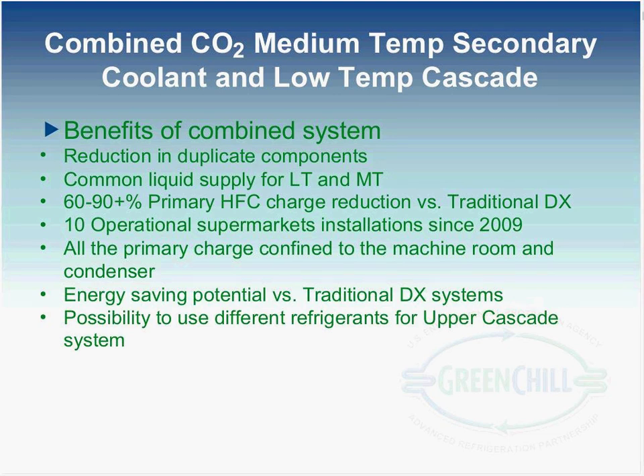Ten of this type of system have been operational since 2009, so it is a relatively new technology, but with good experience to date. Some energy saving potential here, especially on the low temperature system. The CO2 is a tremendously efficient refrigerant. You're able to increase the saturated suction temperature, the compressors run a little bit warmer, and you're able to save some energy over a traditional DX system. And leading to Masood's discussion here, there's a possibility to use different refrigerants for this upper cascade system. So it gives you different opportunities for your upper cascade rack or that system that's condensing your CO2.